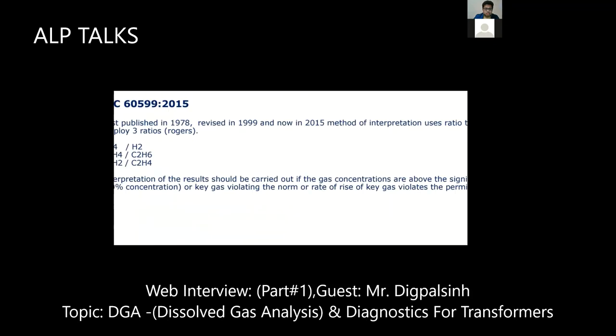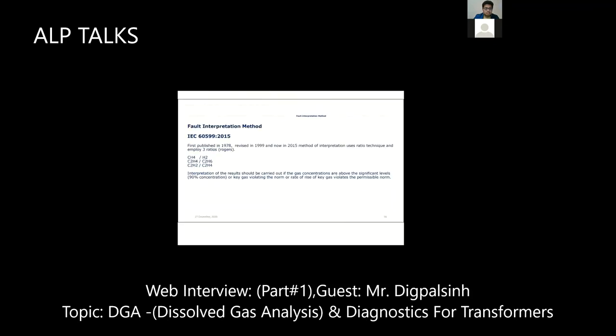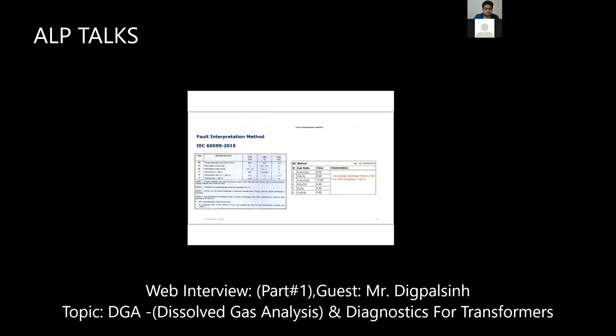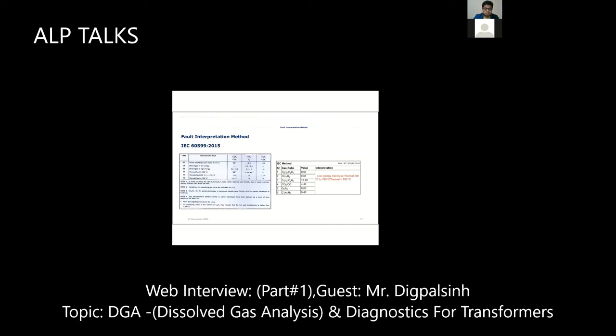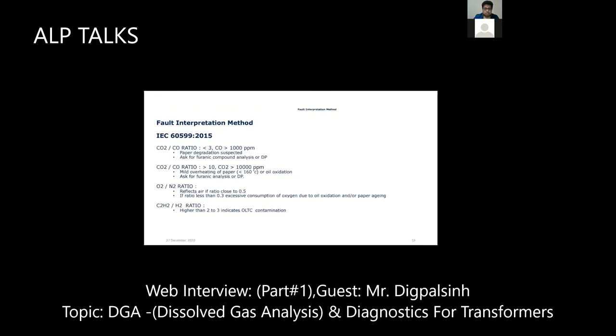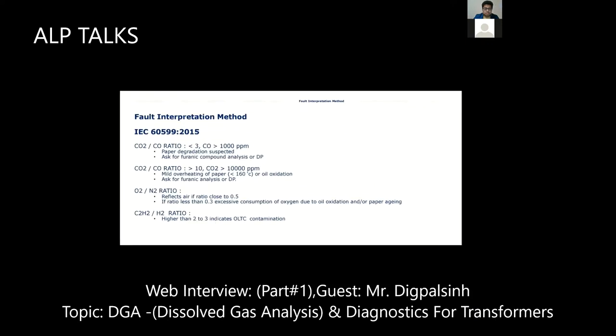IEC has given the major three gas ratios, but from these three ratios you cannot go into depth, for example if some moisture is there or your cellulose, your paper insulation, is involved. To find this out, they have also discussed the ratio of carbon dioxide to carbon monoxide. If it is less than 3, then the DP value is degraded. It should be in between 3 to 10. In short, if your transformer is healthy, the value is in between 3 to 10.